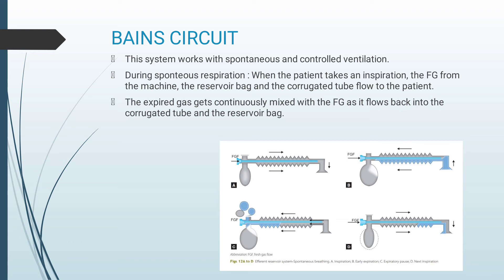The expired level of carbon dioxide depends on the ratio of minute volume and fresh gas flow. If expired volume is greater than fresh gas flow, expired CO2 is determined mainly by fresh gas flow. If fresh gas flow is greater than minute ventilation, end-tidal CO2 is determined mainly by minute ventilation. Recommendations are that fresh gas flow should be 1.5 to 3 times the minute volume so that maximum fresh gas is administered and re-breathing is minimal.